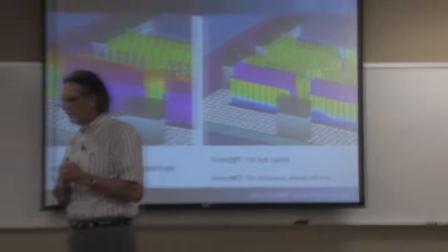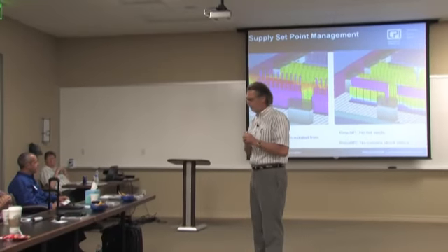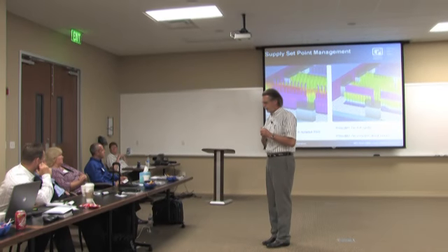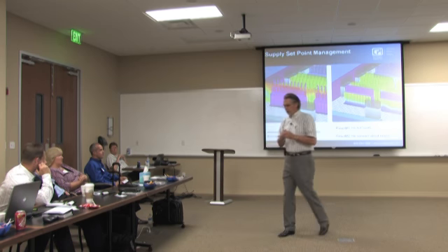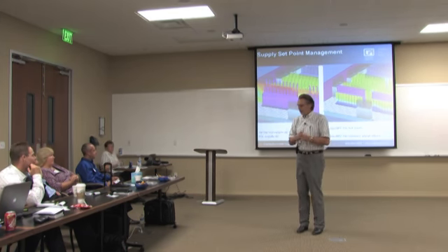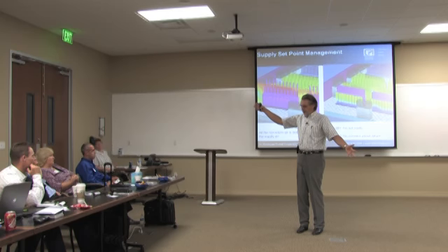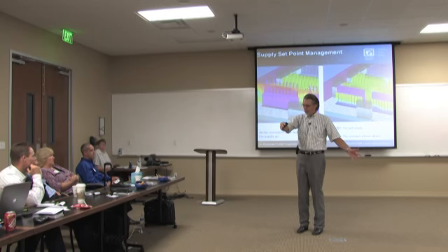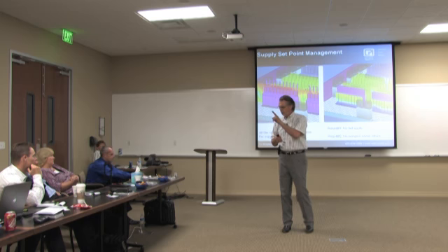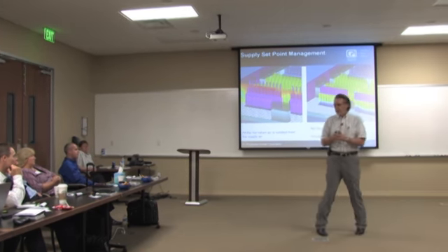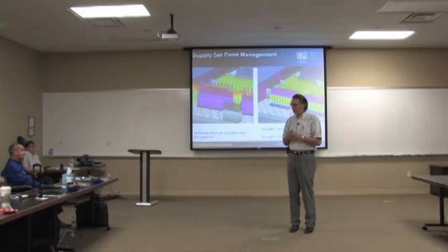So does that mean you have a greater differential between supply and return air? Yes, it does. Okay, so it gives you the opportunity to raise the supply air temperature? Yes, it does. So you can reduce the possibility of condensation. Yeah, we'll do all those things. We'll have a greater temperature difference going through the coils, but we'll also be able to raise the temperature of the air coming out of the coils.